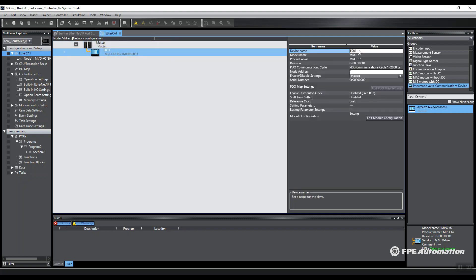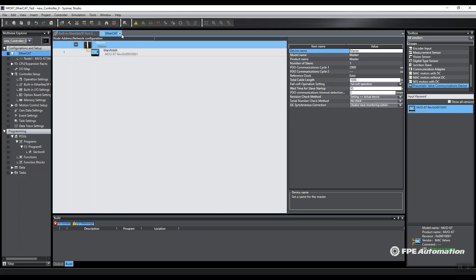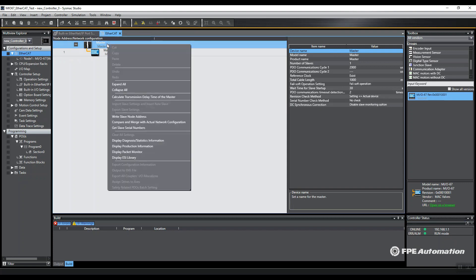Now by default it's going to be called EtherCAT 001. I'm going to name this whatever name I'd like, and out of the box the communications driver has a slave address of zero. I can write whatever node address I'd like to it, and then I can go online and right click to do write slave node address. This is how you can set up a unique address for multiple manifolds. Please note that once you write a slave address you have to do a power cycle.